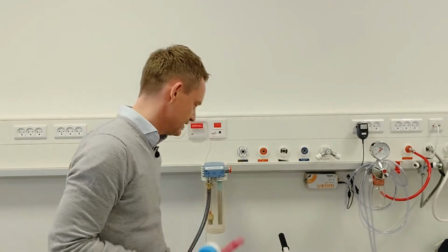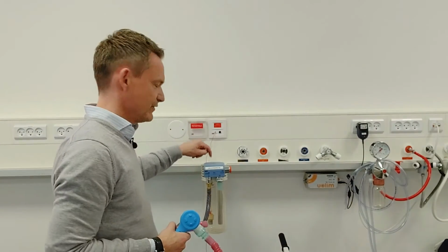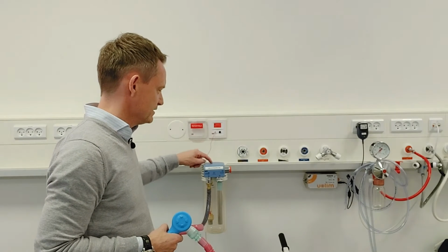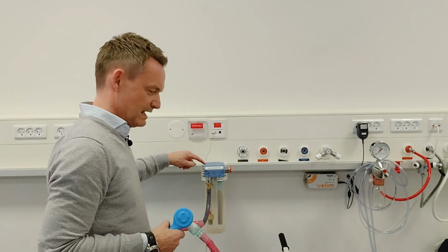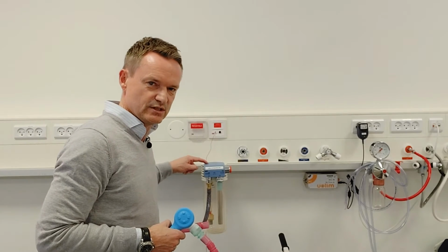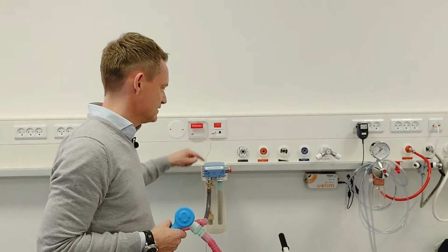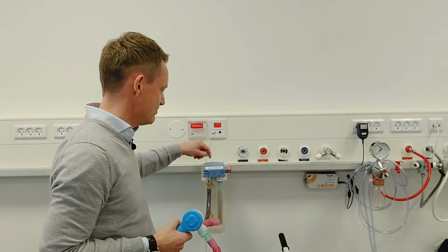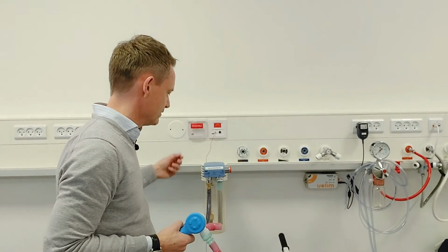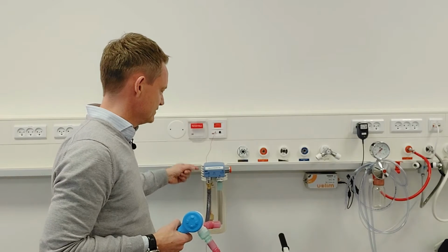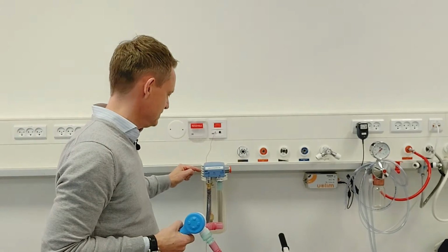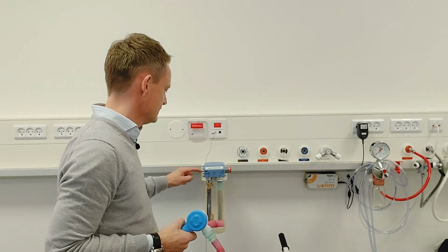So what I will do here is use a buffer, and the buffer is to make sure that I do not do something wrong to the patient. So in between these connections, both the AGSS and my demand valve, I need to have a buffer. And this is what it's called, it's a buffer. What you see here from this buffer is that it has holes on both sides, and they need to be there because they will protect the patient.